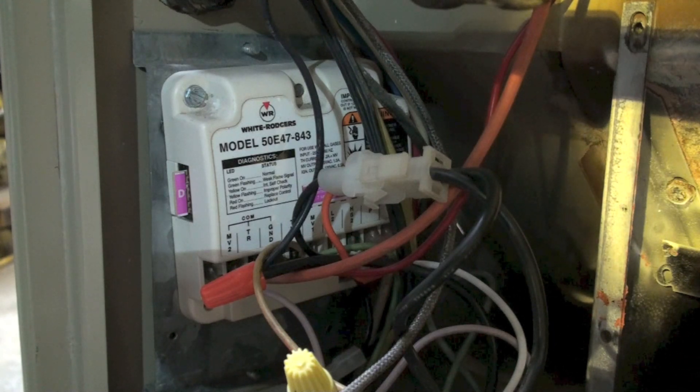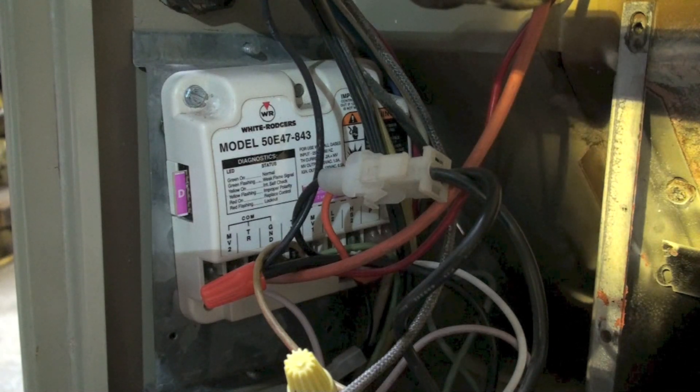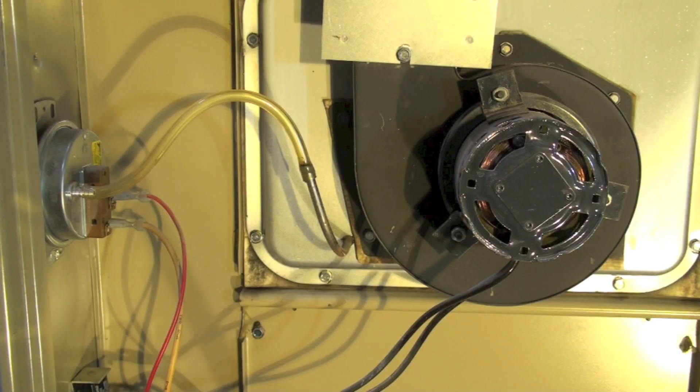Now here's one of the common reasons for this. My inducer's running, pressure switch is right here. But did my pressure switch make?